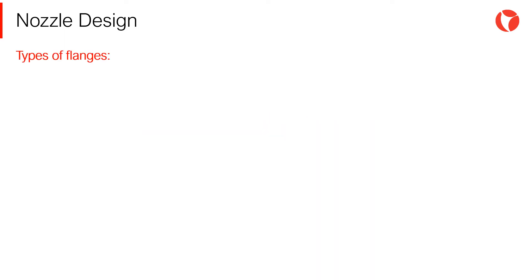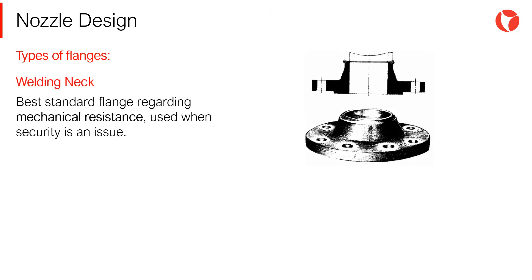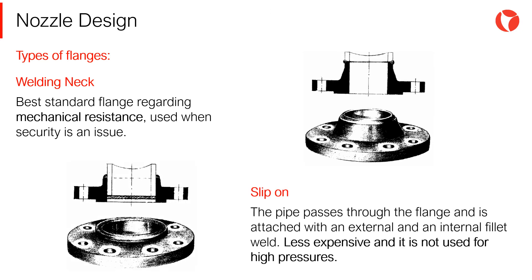Some of the flange types most used in pressure vessels are: welding neck flange, butt-welded to the pipe — the best standard flange regarding mechanical resistance, used when security is an issue. Slip-on flange: the pipe passes through the flange and is attached with an external and internal fillet weld. This type is less expensive than the previous and is not used for high pressures.